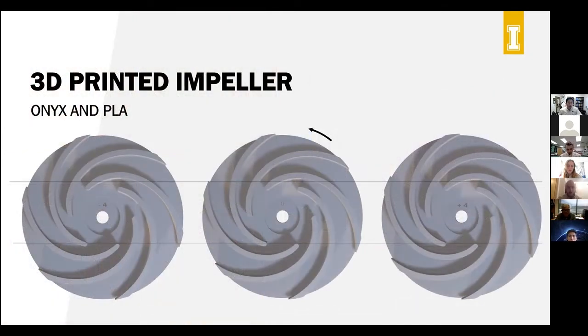And here it's kind of a comparison of the angles and of the change that we made on the impeller. On the left impeller, you can see just below these two reference lines on the top one, how it's just a little bit below the line on the left side. And then the middle one is our stock impeller. And on the right, it's a little bit above the reference line. And these are the three impellers that we actually 3D printed and tested to see how the angle change would affect the efficiency of the pump.